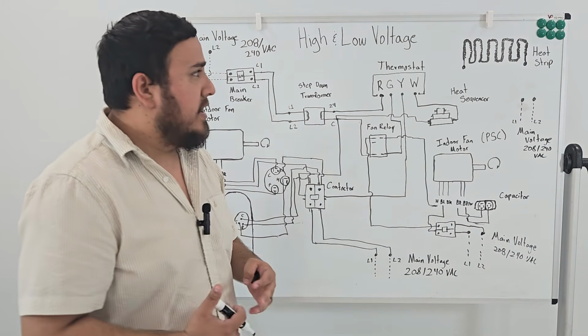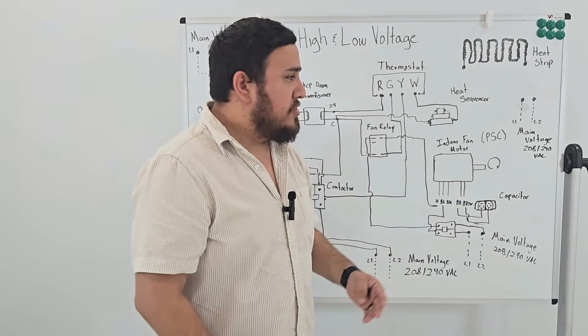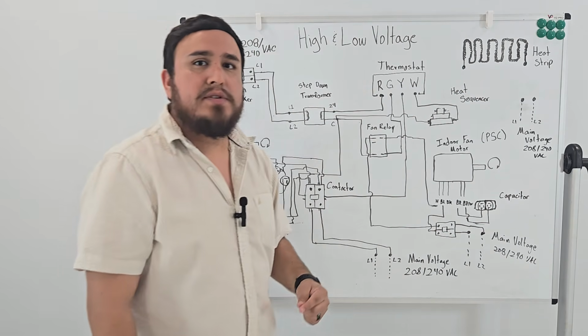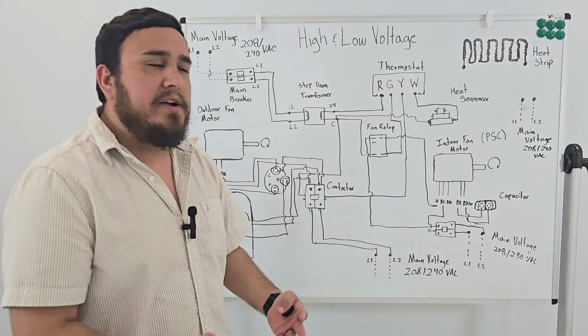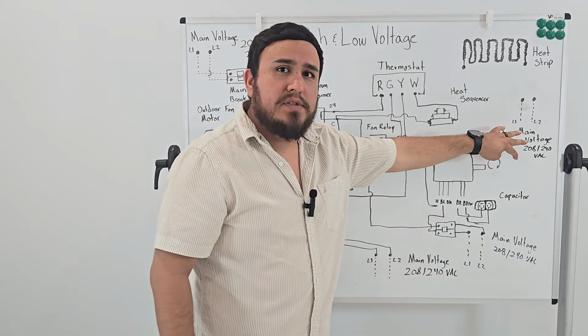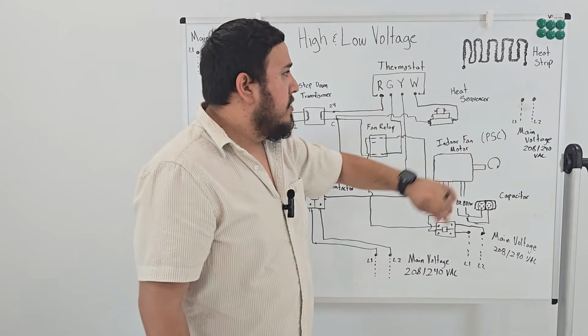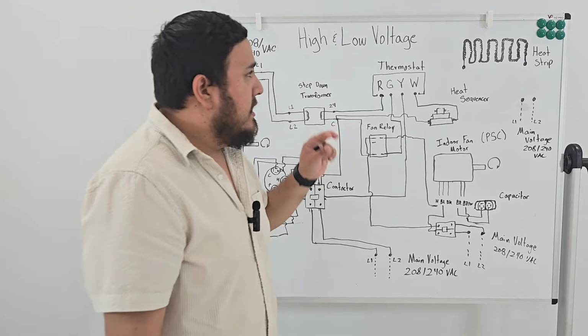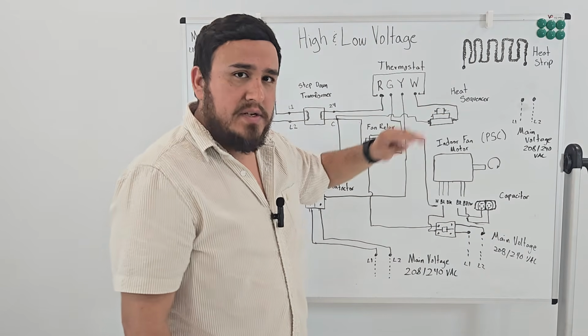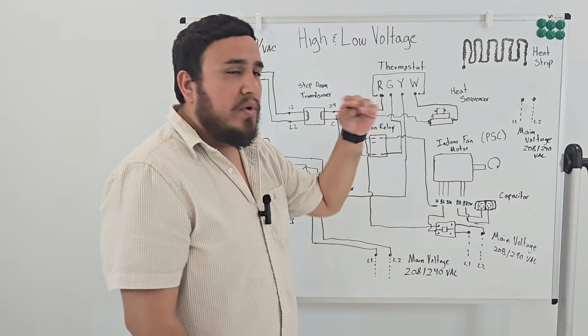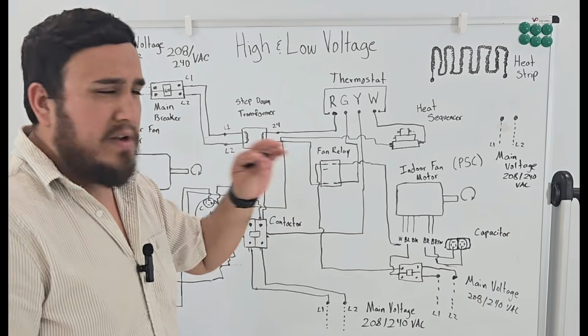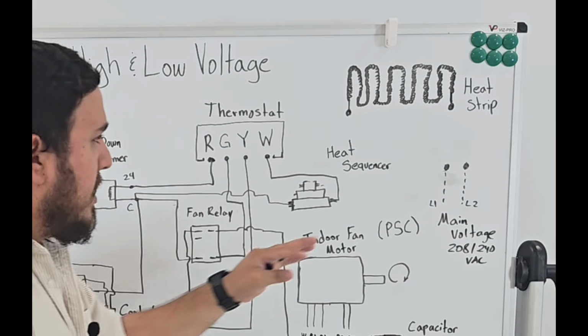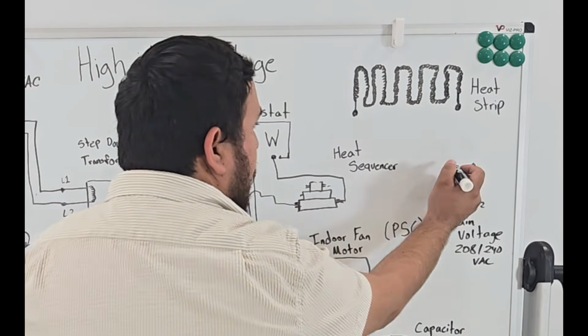Our last connection is the heat strip. For the heat strip, I'll use my heat sequencer to control the heater. I have my main voltage here, and I'll send line 1 through the top stack of the sequencer, then bring line 2 through the other side. Let me show you how that's done, starting with L1 right here.